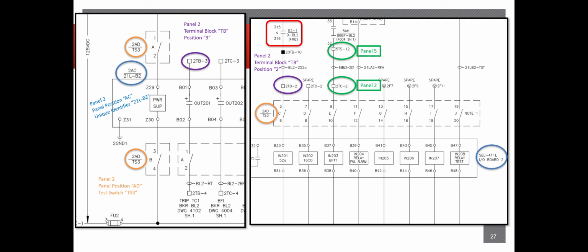So like I said, the anti-pump scheme is a protocol that we use to hook up the wiring a certain way so that you can only close a breaker once, unless it's a reclose initiate scheme, which is an entirely different set of contacts that will come in.